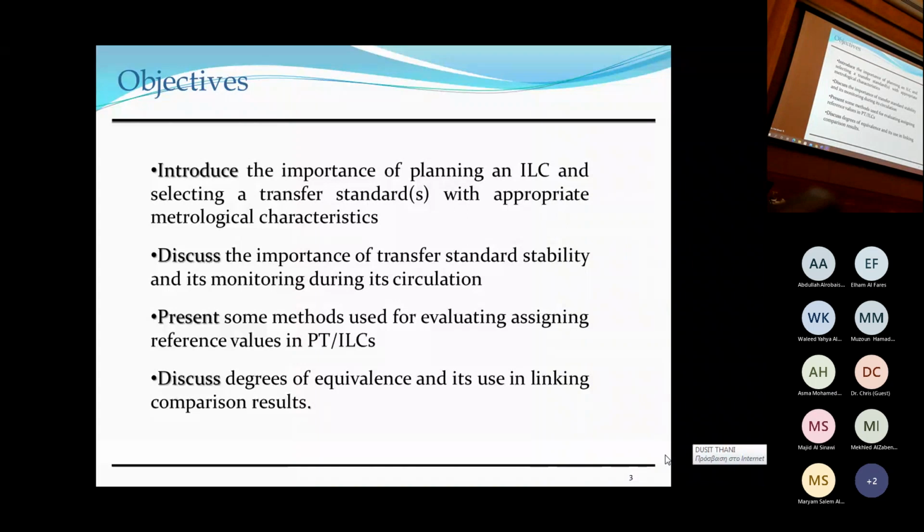A PT is something where the end result is pass or fail, and the decision is based on the results of an ILC, whereas an ILC has no pass or fail component associated with it. It's a comparison, typically for high-level laboratories, with the average of all of the participants. So it's based on consensus, typically. But it doesn't have to be that way. But usually it is.